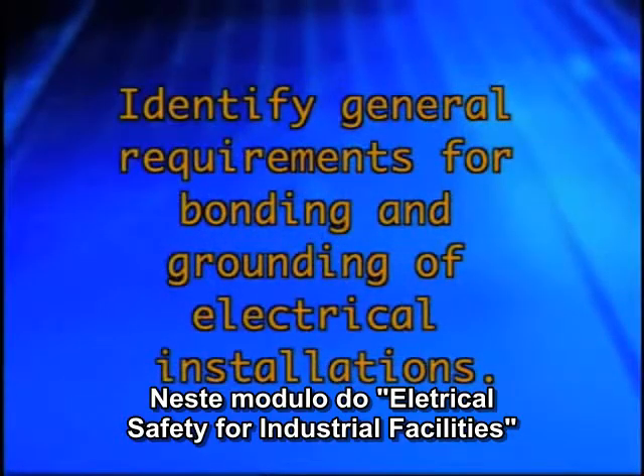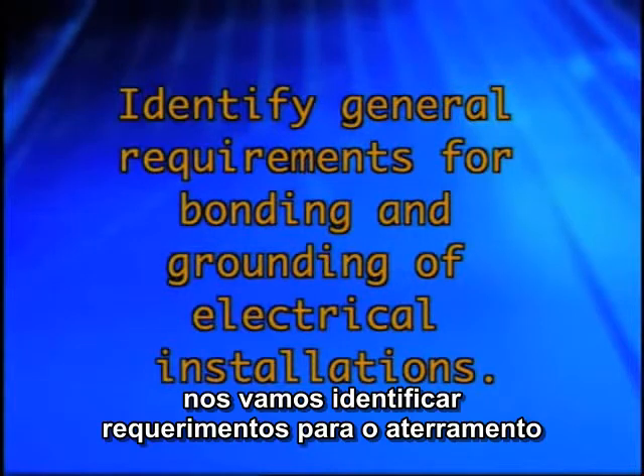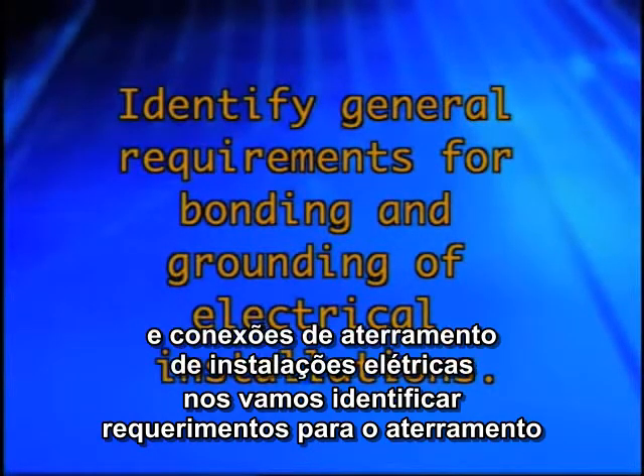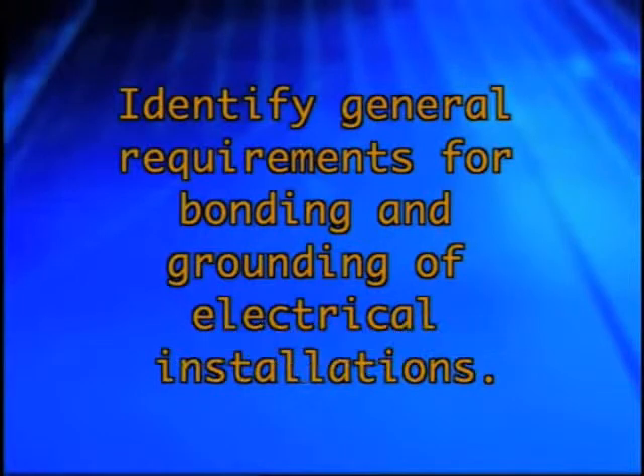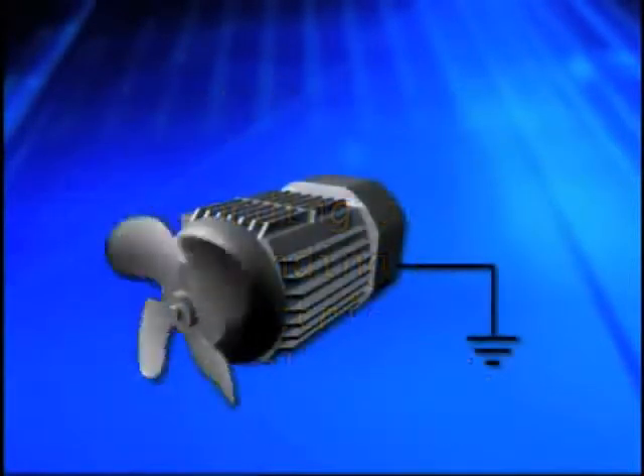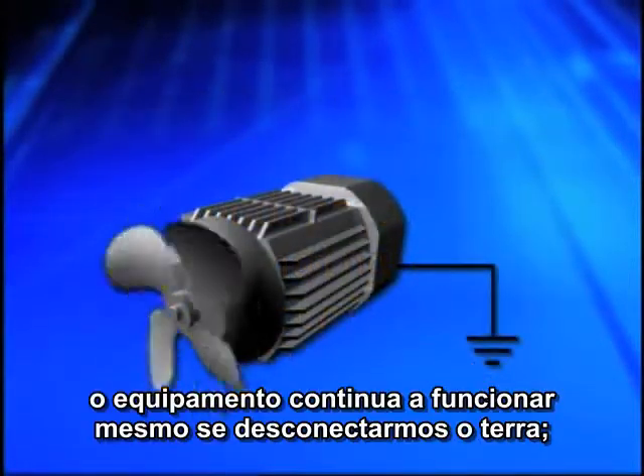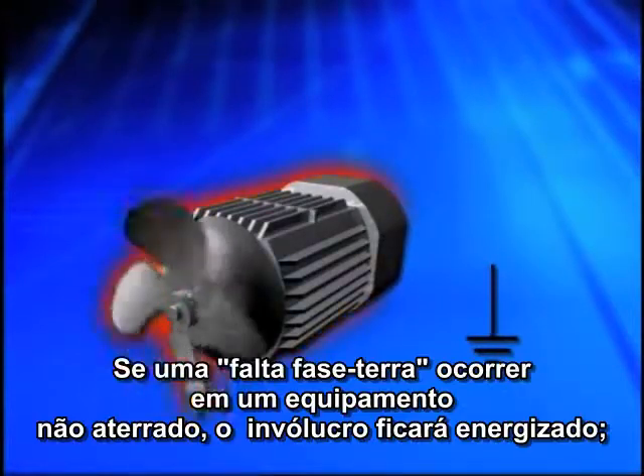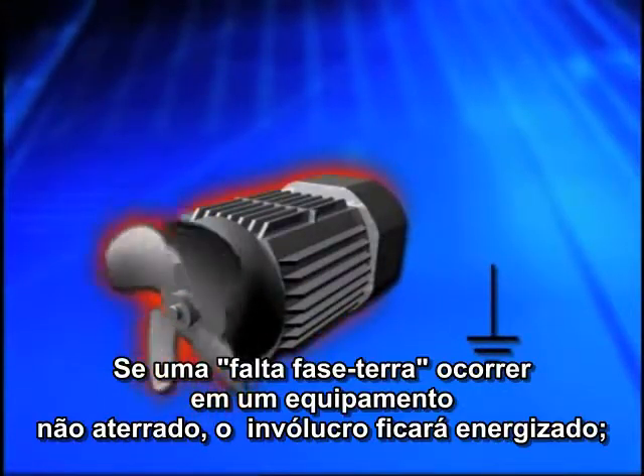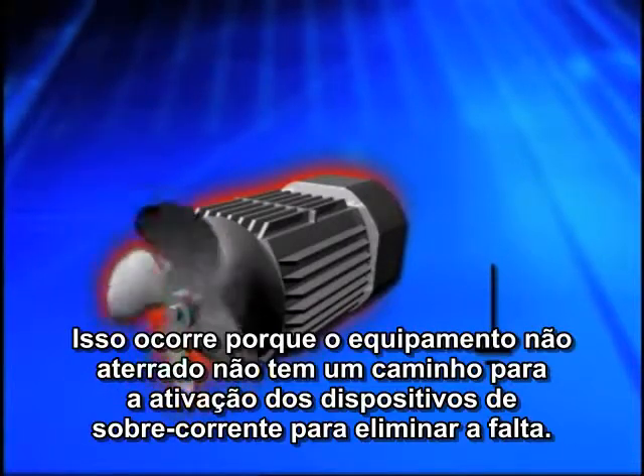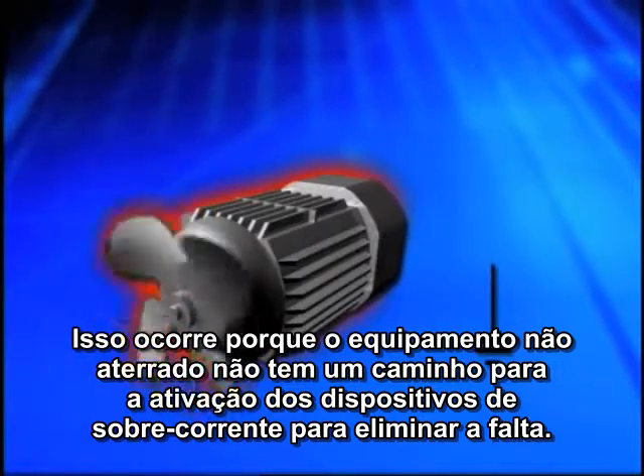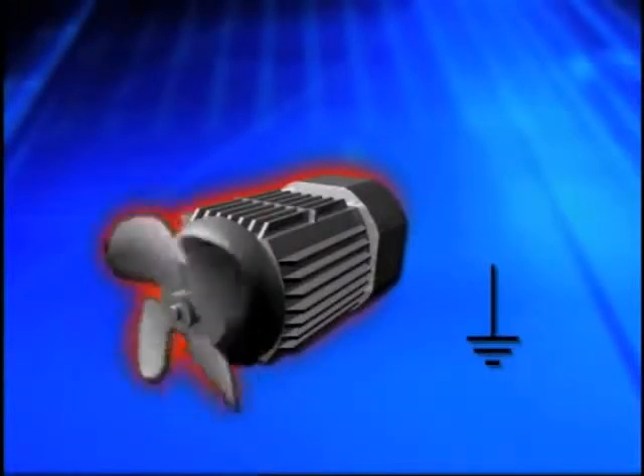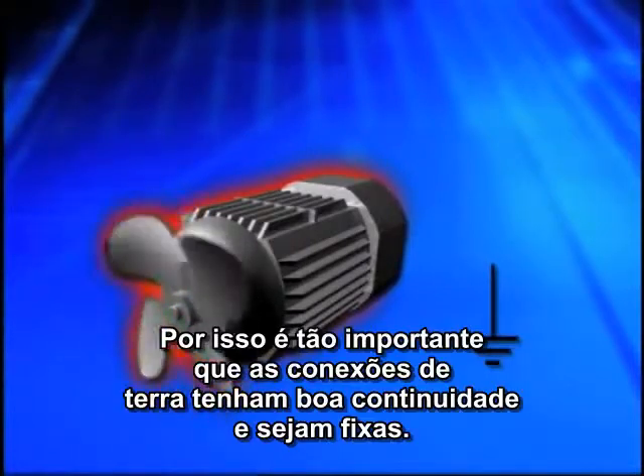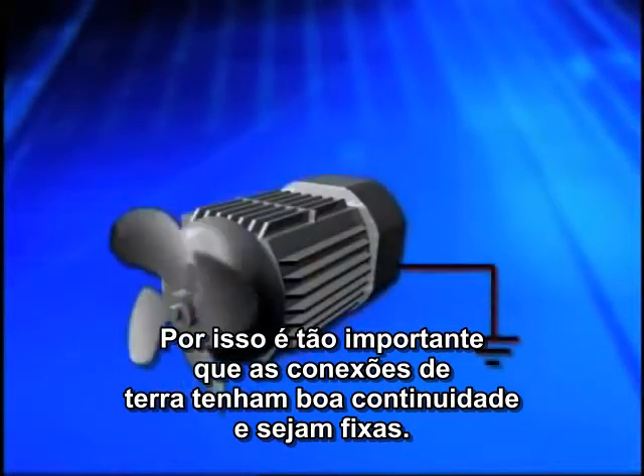In this segment of our Electrical Safety for Industrial Facilities series, we will identify general requirements for bonding and grounding of electrical installations. As we all know, equipment continues to function even if the ground becomes disconnected. If a ground fault occurs on ungrounded equipment, the equipment enclosure becomes energized. This occurs because ungrounded equipment does not provide a path back to the system to cause the overcurrent protection device to clear the fault.